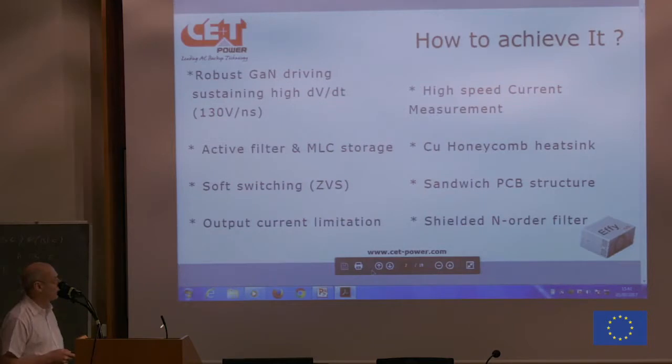By assumption, we had to develop a current output limitation, because we know from experience that an inverter without current limitation is a nightmare. You never know what you have as a load, even during test. If it is defined at the moment of switching, you can have capacitive effect and things like that, so overcurrent. And so it's more likely why the Fraunhofer, which was before us in the top list, has failed at 90 hours. They said it's only a wire, but we didn't see any current limitation in their design.